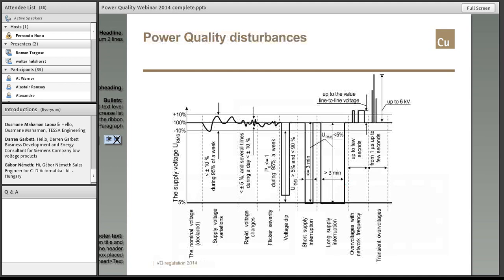Now, this is a chart presenting most of the disturbances covered by EN 50160. So we've got, from the left, nominal voltage, then supply voltage variations, then rapid voltage changes, then flicker severity, then voltage dip, and then short interruption and long interruption, which are not voltage quality events. And then we've got overvoltage with network frequency, and then spikes and transient overvoltages. What is not represented by this figure, but is included in 50160, is of course unbalance.